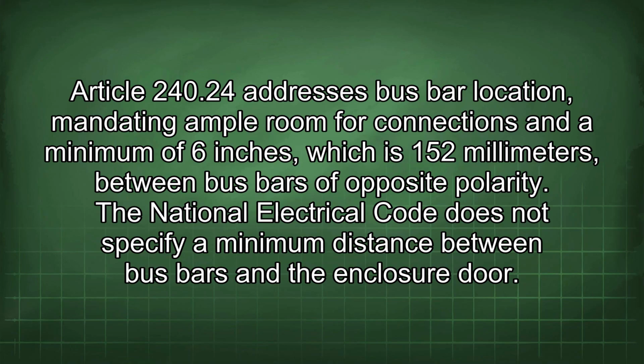Article 240.24 addresses bus bar location, mandating ample room for connections and a minimum of 6 inches, which is 152 millimeters, between bus bars of opposite polarity. The National Electrical Code does not specify a minimum distance between bus bars and the enclosure door.